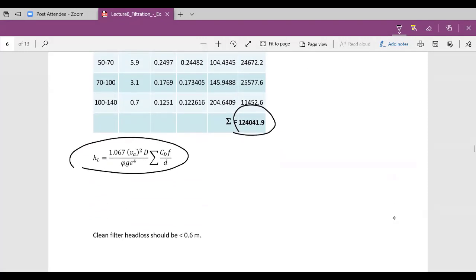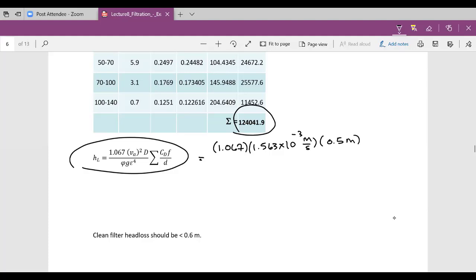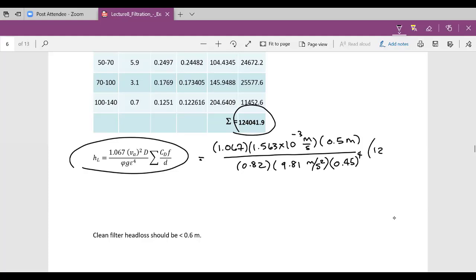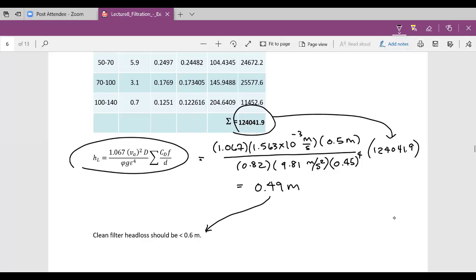We use this equation here to calculate the head loss of the clean filter. This is equal to 1.067 times the approach velocity in meters per second, times the depth, divided by the shape factor, times G, times the porosity to the fourth power, times this summation value. That equals 0.49 meters. Your clean filter head loss should be less than 0.6 meters, so we are good there.